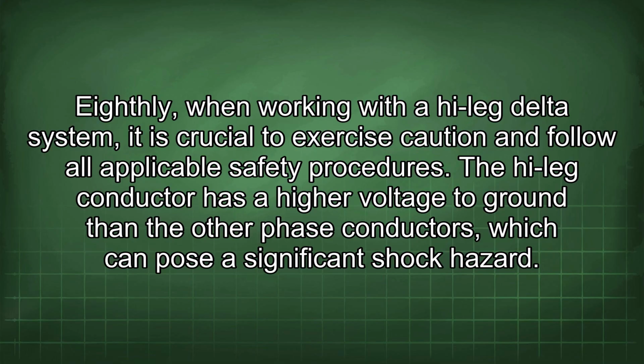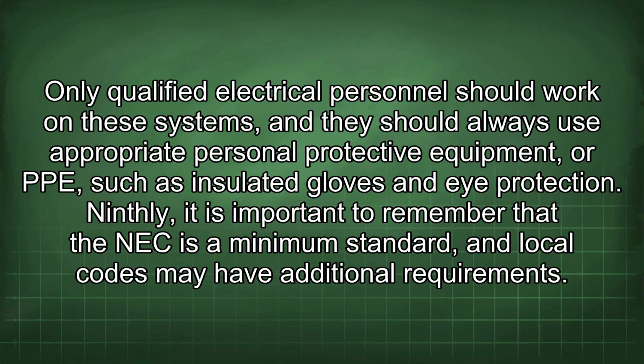The high-leg conductor has a higher voltage to ground than the other phase conductors, which can pose a significant shock hazard. Only qualified electrical personnel should work on these systems, and they should always use appropriate personal protective equipment, or PPE, such as insulated gloves and eye protection.